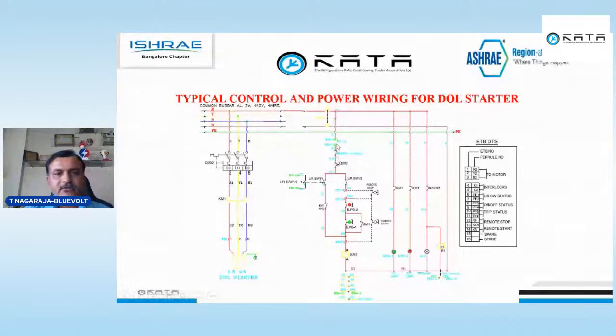These are all the control circuit. All the interlocks will get closed, then your overload relay, then auto manual, then the holding contact, BMS, and remote start stop. Everything is connected in series. Then the contactor will switch on. This is a red and this is a green. Once you press the green, your red indication will come on, and automatically your motor will start running.